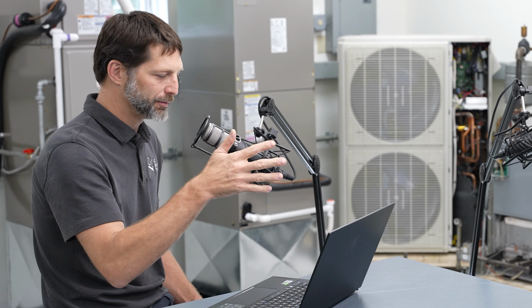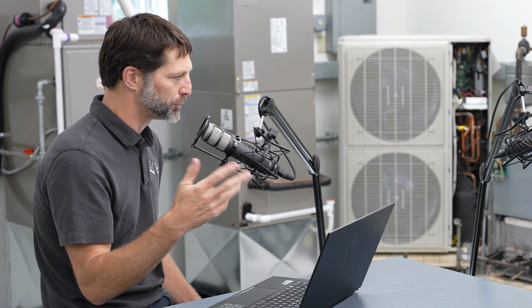Try not to pull through a manifold. You can use a Y fitting and just go right to your vacuum pump. Keep the vacuum gauge at a location where you can shut the valve core removal tool off and measure the vacuum of both zones or just one.